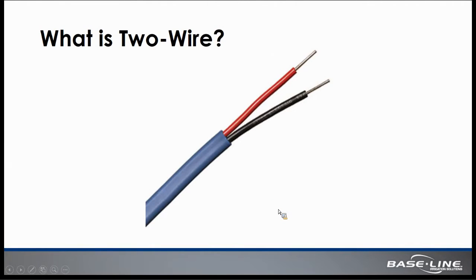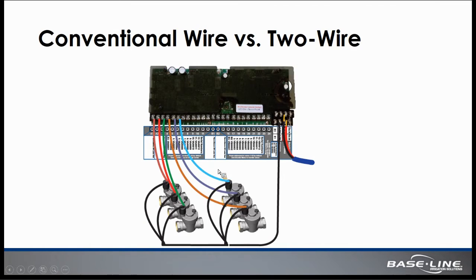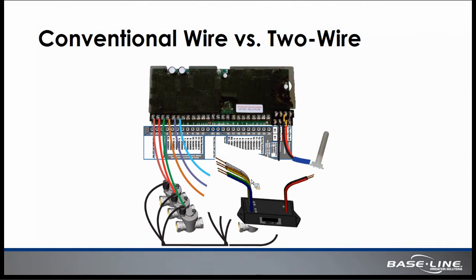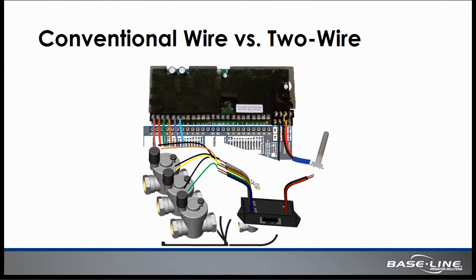So as we look at two-wire and define what two-wire is, I would hope that most of you have had some exposure to two-wire at this point, but two-wire is literally just two wires. And rather than having a conventional system where you have a hot wire and a common wire running from each of the irrigation control valves back to the controller, you have in place a two-wire path with decoder devices that then interface with those valves to perform irrigation functions. So it's a much more streamlined configuration or design that allows the system to operate while minimizing many of the materials that may normally be required with a conventional wire system.